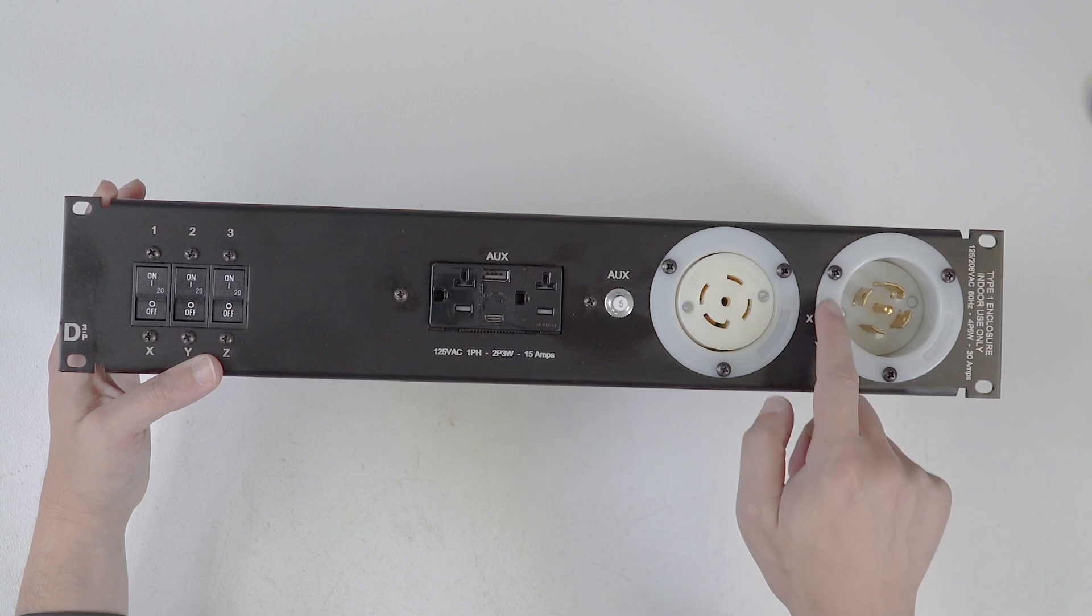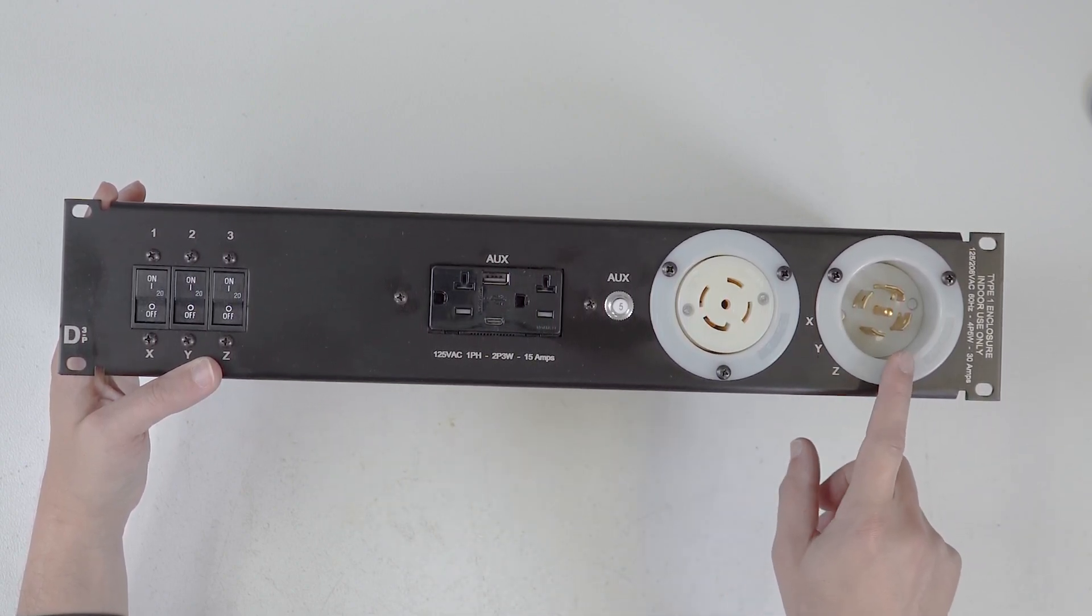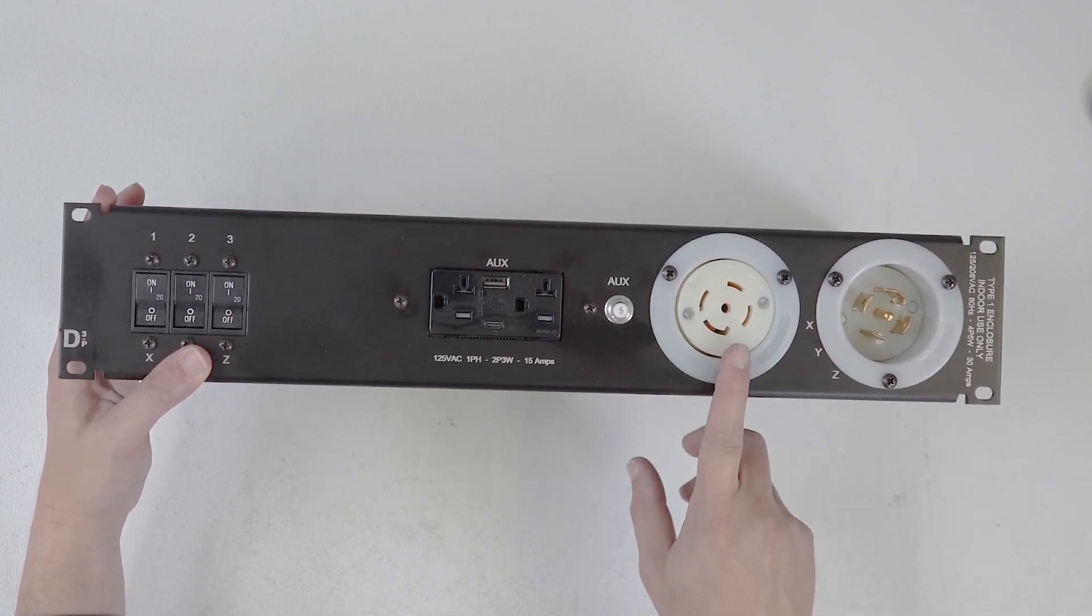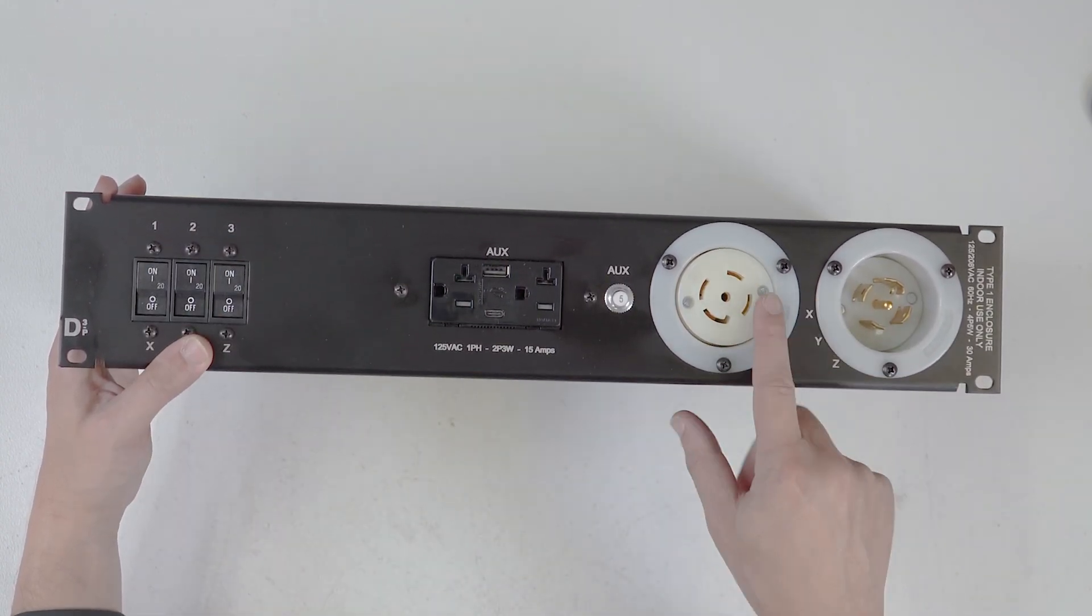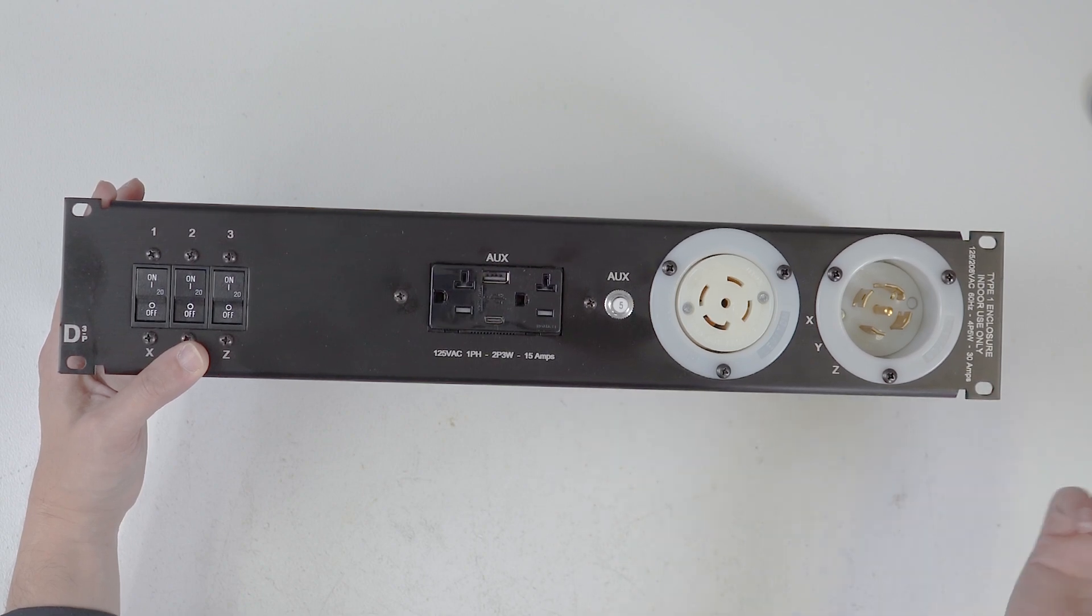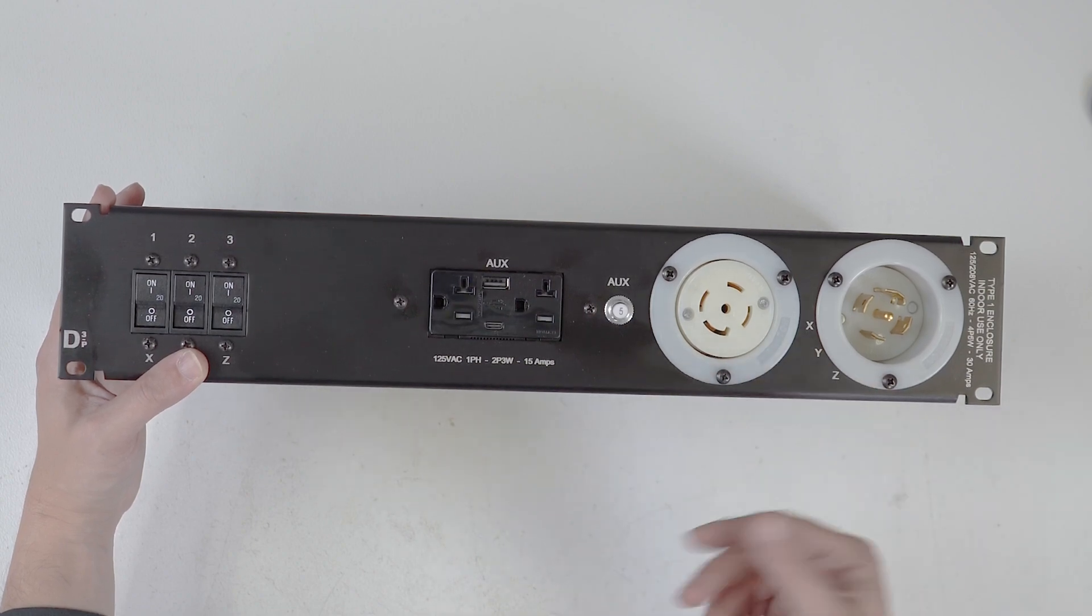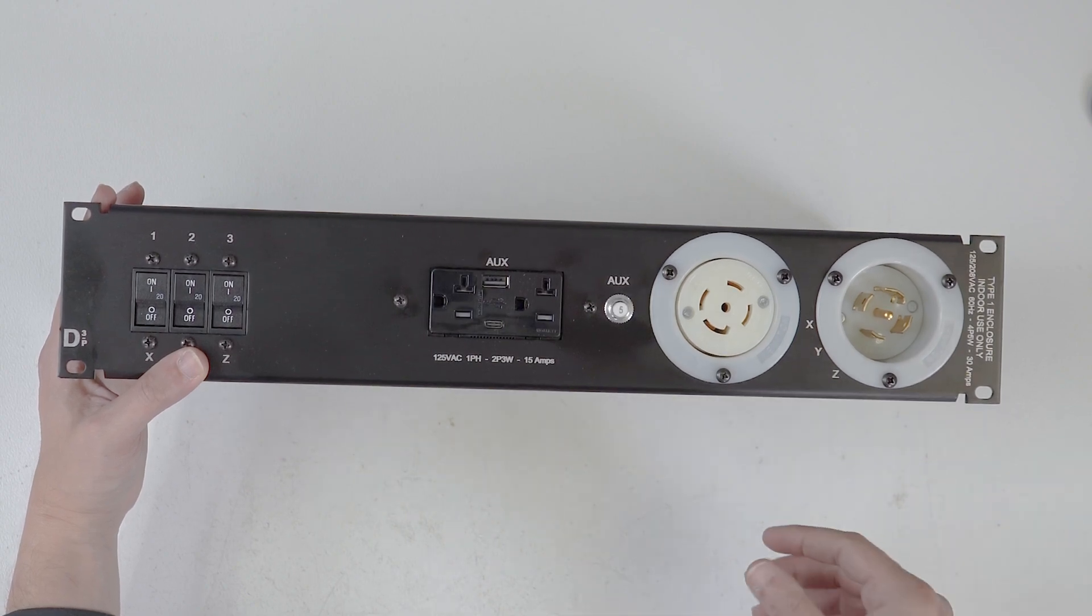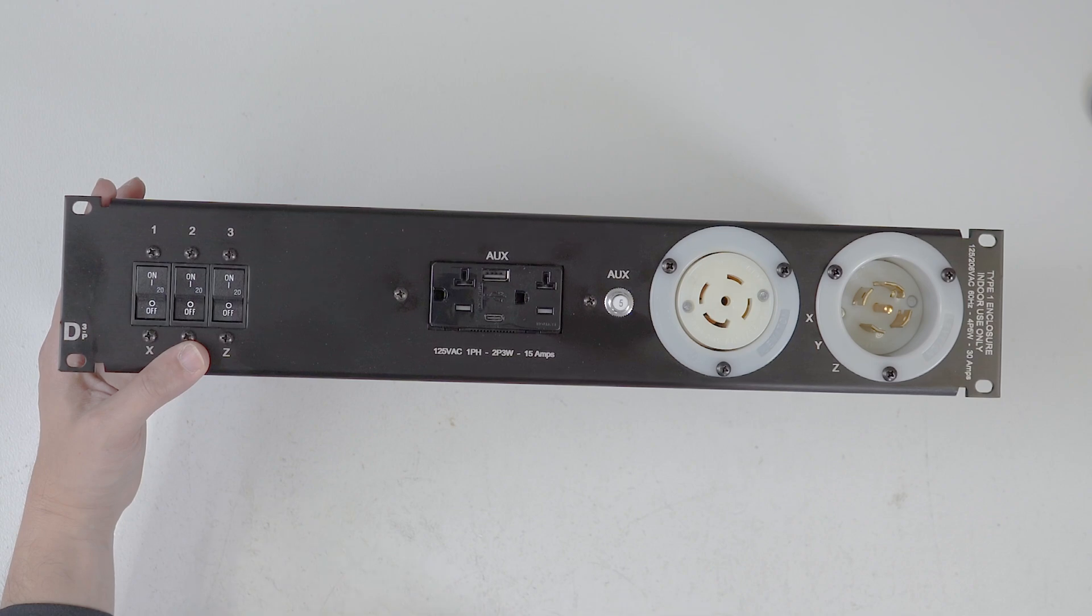Anyway, L2130 input. Three LED lights right here for X, Y, and Z to let you know that there is power at each leg. There is a looped output on this. This is wired pre-breaker so that if you do want to loop these together, you can. So, the breakers being tripped here will not affect the amp racks down the line. I've gone back and forth on how to do that. Some days it makes sense to me to wire this post-breaker and other days it makes sense pre. I always ask customers how they'd want it wired and 9 out of 10 times most people say, I want this pre-breaker so that if you lose a leg, you only lose one rack. You don't lose everything down. Or I should say at least because of a popped breaker.